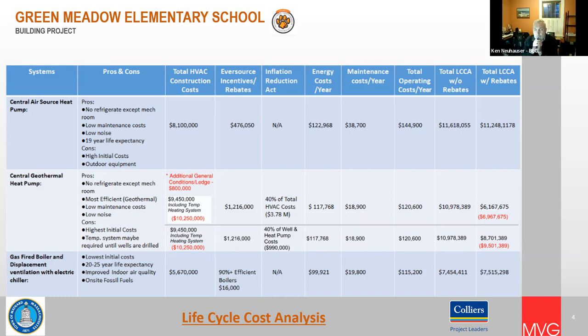And what temperature hot water would that be? We try to design around low temp, depends a little on the envelope, but it would probably be in the 130 degree range, maybe 120. Trying to keep the boilers condensing as often as possible. Right.